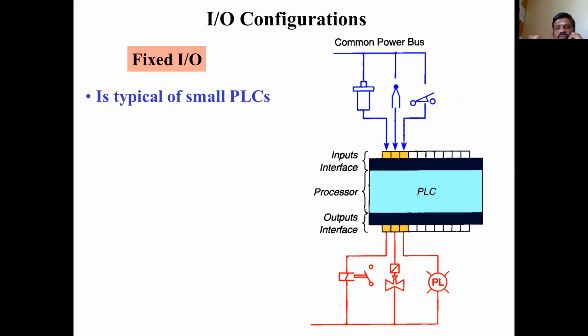This is not widely used for controlling many things, because it has limited inputs and outputs. It will have a maximum of 8, 12 or 16 inputs and 8 or 12 outputs. Even though 8, 12, 16 will be a large number when it comes to a laboratory, if we go for an industry, this is a very minimum input and output.